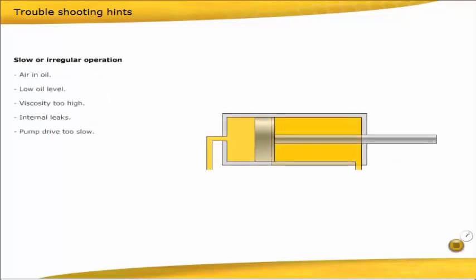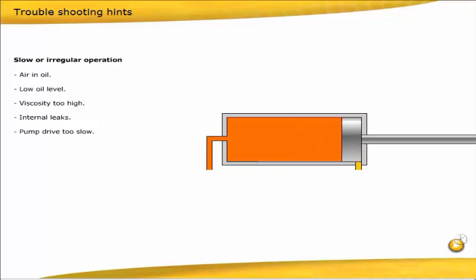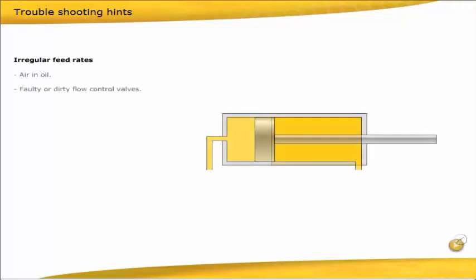Slow or irregular operation. Air in oil. Low oil level. Viscosity too high. Internal leaks. Pump drive too slow. Irregular feed rates. Air in oil. Faulty or dirty flow control valves.